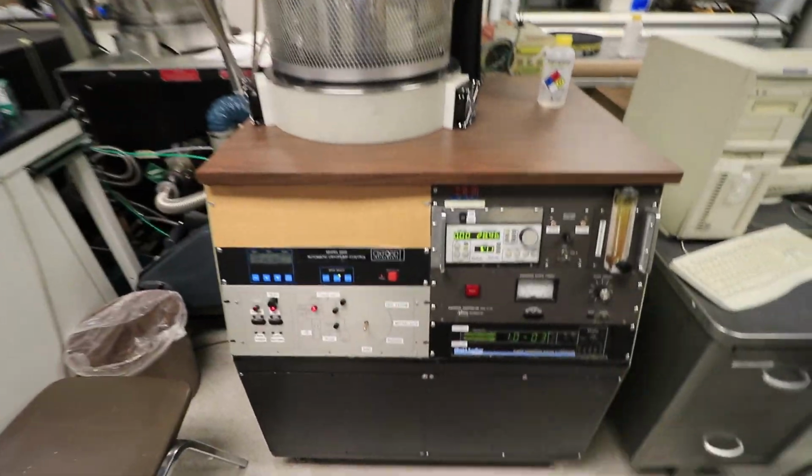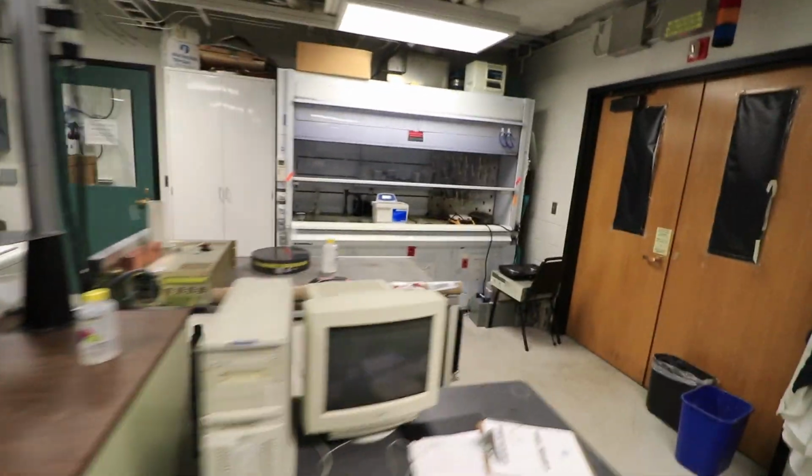There's a semi-automatic thermal evaporator dedicated to the evaporation of indium. This system operates under computer control and supervision, allowing for thick films taking more than 8 hours to be carefully and slowly deposited. This is particularly useful for the realization of indium bumps and the patterning of laser submounts.